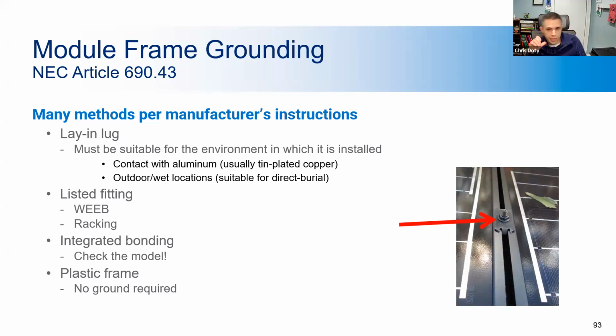At the array, the bonding and grounding are very important issues, as I mentioned like 25 times in this presentation. As discussed earlier, the bonding of equipment provides the pathway for fault current to open an overcurrent device or be detected by the fault detection equipment, which will disconnect this fault from the system or from the equipment.